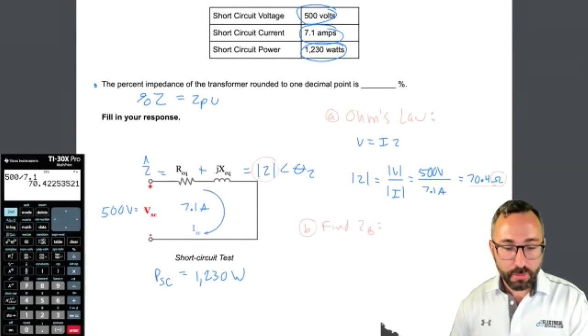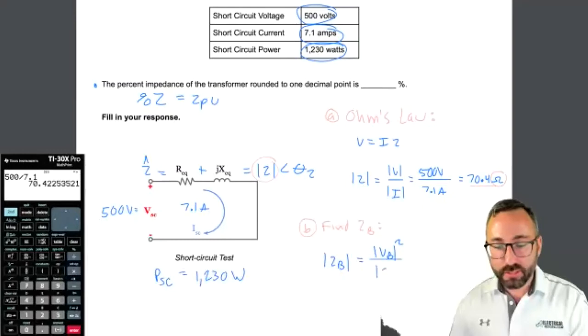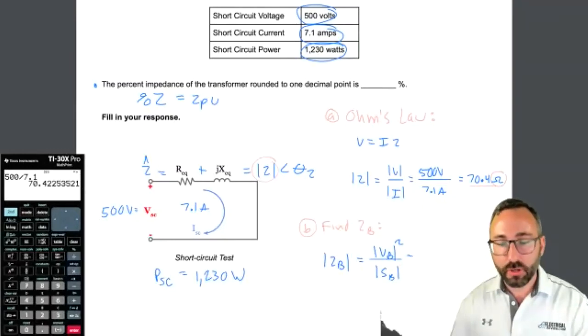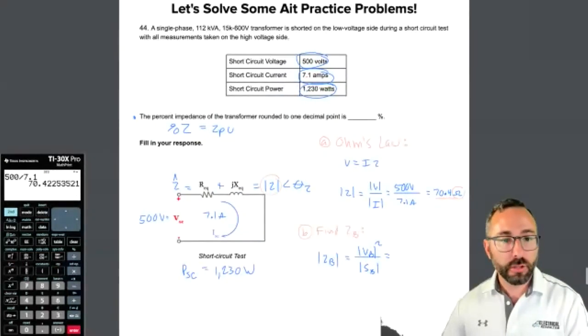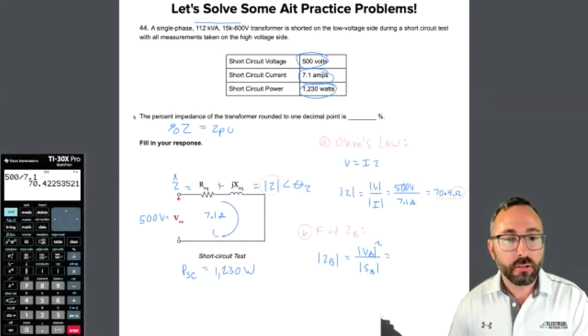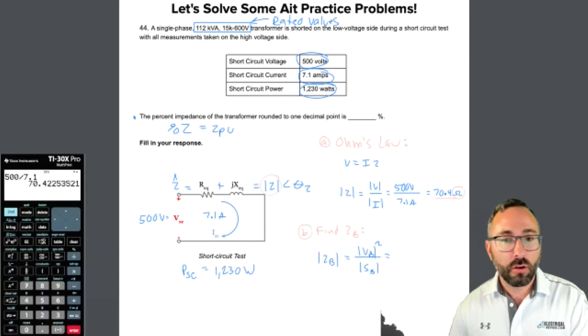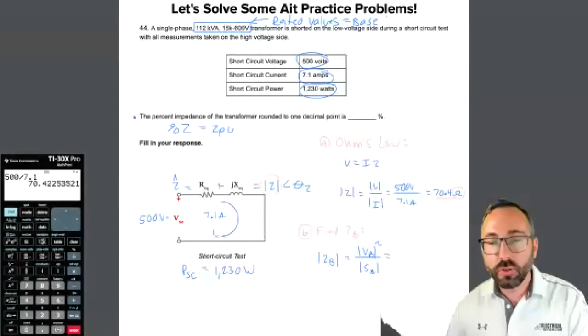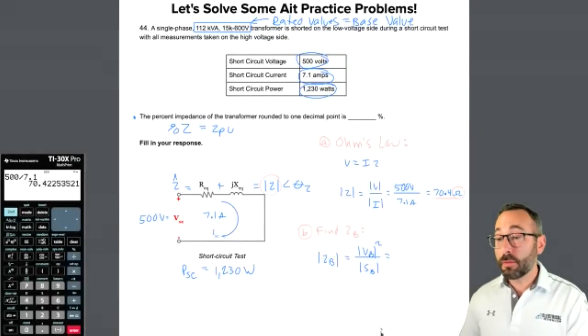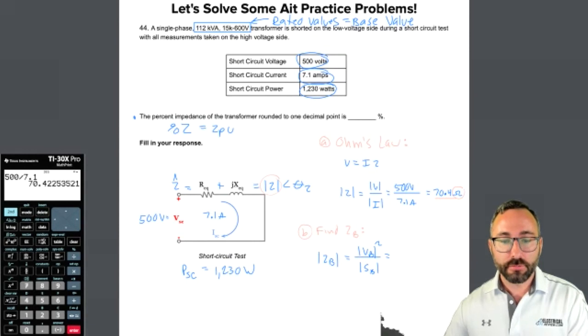All right, I can find the base impedance, ZB. It is the square of the voltage base divided by the power base. Where do we get these values from? Let's go back to the problem. Look at this. Here's the ratings of our transformer, right? 112 kVA, 15,000 to 600 volts. The rated values of a machine are the base values that are used to express its percent impedance value in. So here's our base values.